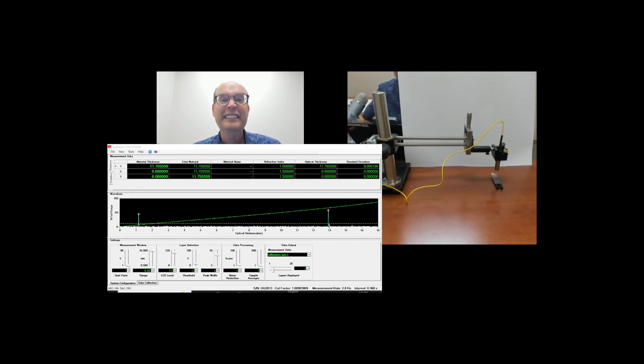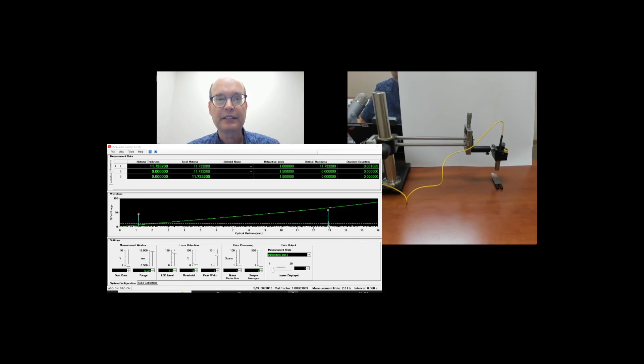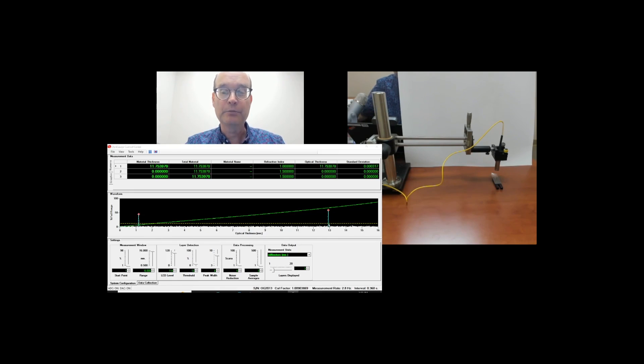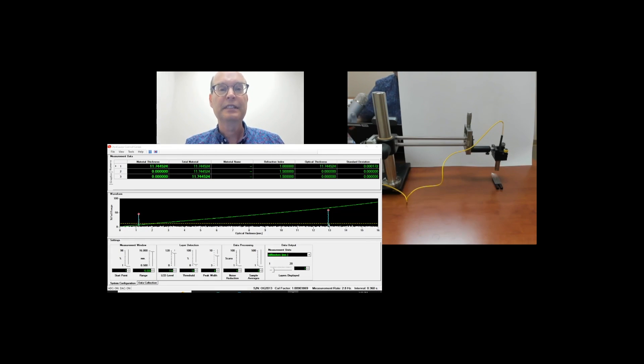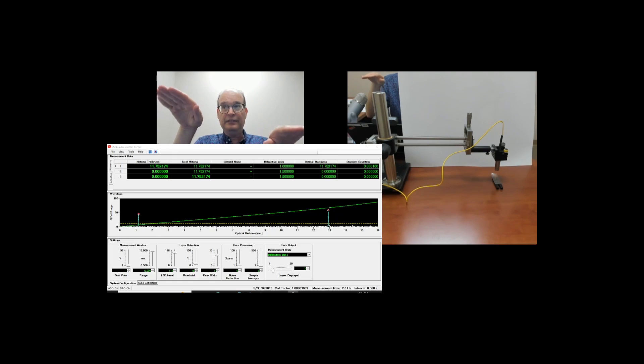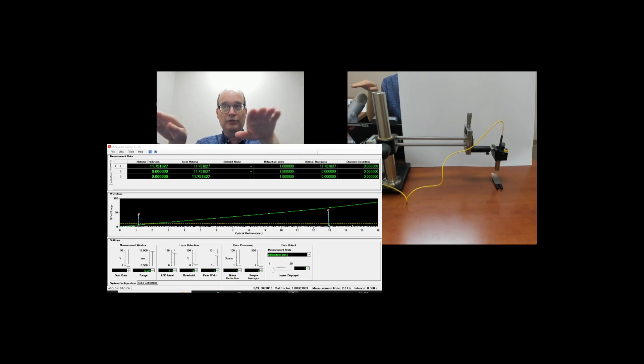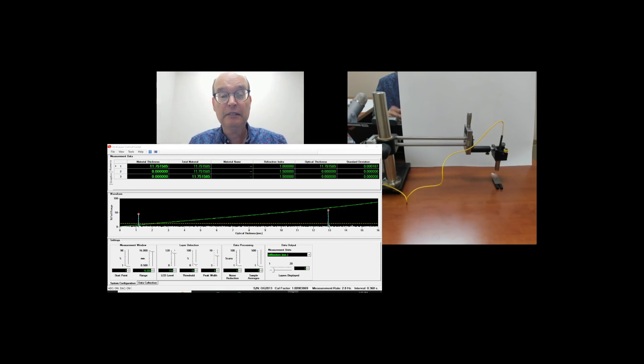Looking at the data, it looks like I have a tilt in my stage as I transfer from one end to the other. I'm going to show you briefly how I calibrate that, because I can use it to back out the tilt I see from the stage movement. In other words, the stage isn't level — it rises and lowers as it moves across. But a linear adjustment can be made to just take that out.